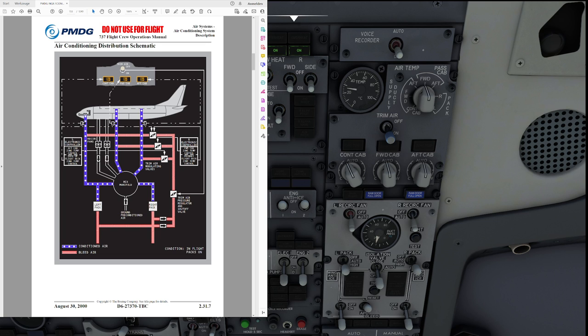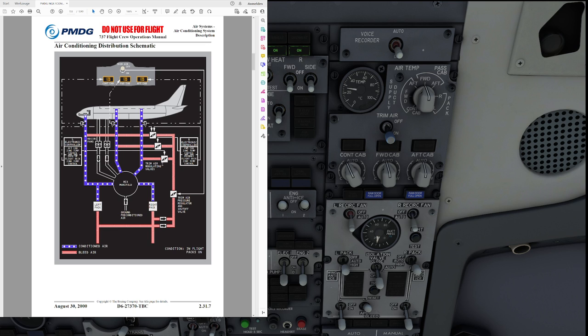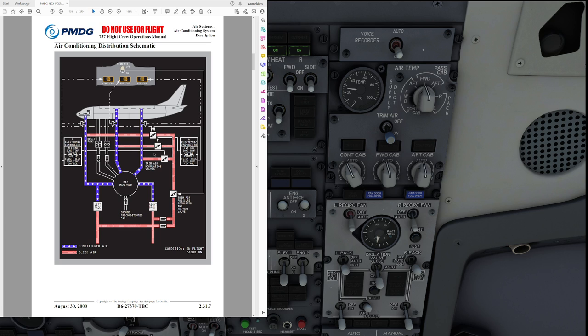Let's have a look at what this means. Air from the mix manifold is being distributed to the supply ducts into the cabin but after the mix manifold it is being mixed with trim air through the trim air modulating valves. Now, the flow of air is no longer right from the packs through the mix manifold to the cabin but actually from the packs into the mix manifold and thereafter air is being mixed with hot trim air that's been taken from the system prior to the packs in order to heat the air up as necessary.